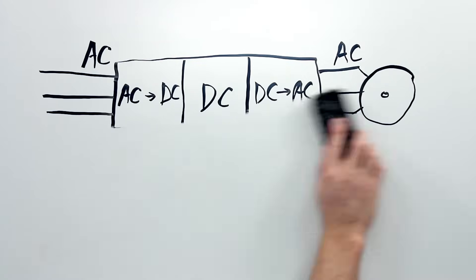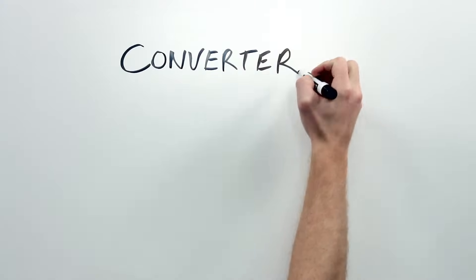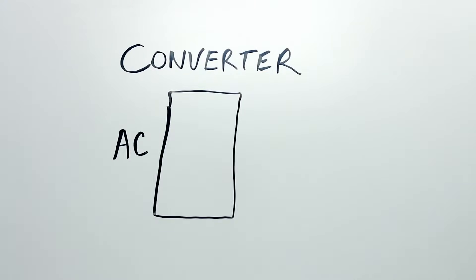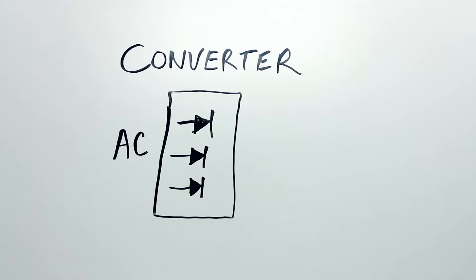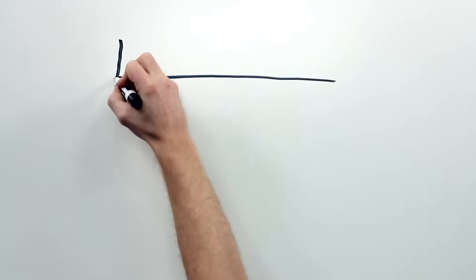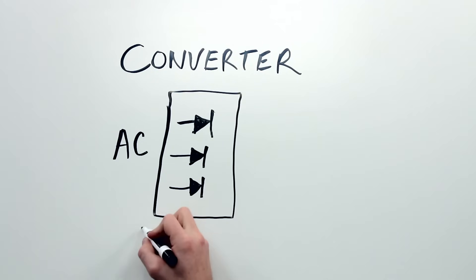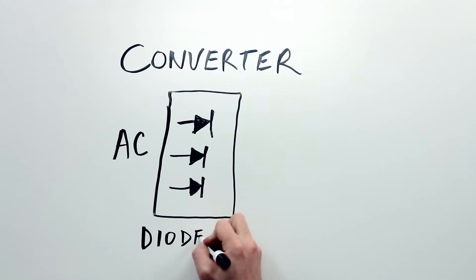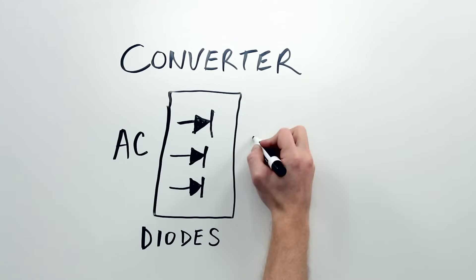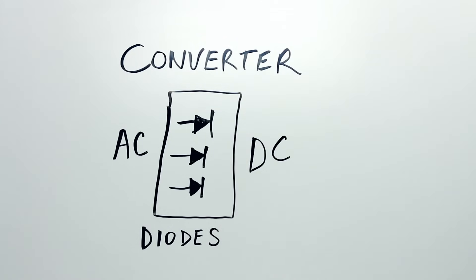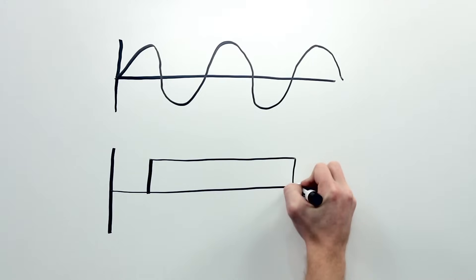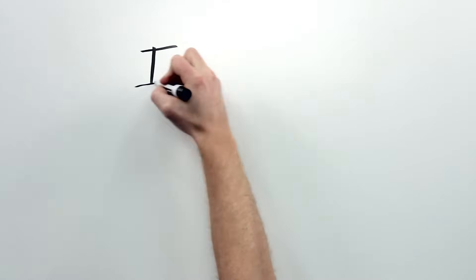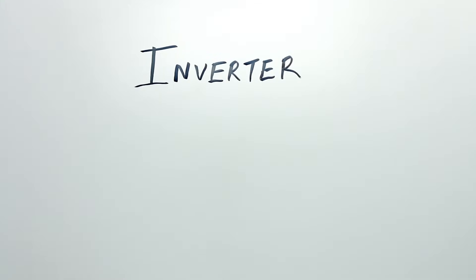That seems like a lot of work to take AC power, mess around with it, and then spit it back out. So let's figure out why. In the converter section, we have nice clean AC power coming from the utility on one side. Inside the converter, there are diodes that chop up that AC power and spit it out as DC. We use capacitors inside the drive to smooth out this DC so that the power looks flat until it turns off. Then the DC power gets onto the DC bus, which carries it over to the inverter section.